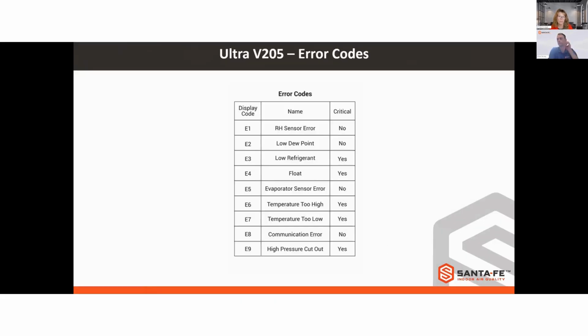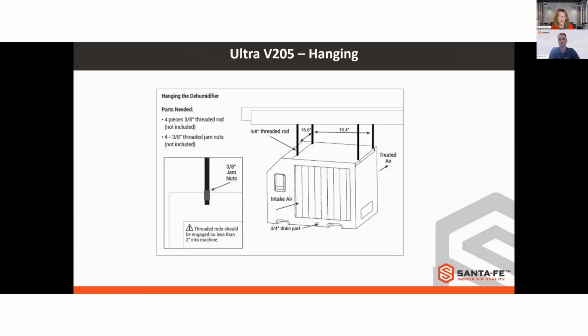And this one, we're going to give you some error codes as well. These are all going to be displayed with an E and a number next to them. And we will indicate to you which of these would be more of a critical code, meaning that the unit is no longer producing water and what needs to be addressed immediately. And different than all of our other units, you are actually able to use a 3/8 threaded rod directly on this unit in order to hang it. So you do not have to purchase a separate hang kit to go with this unit.